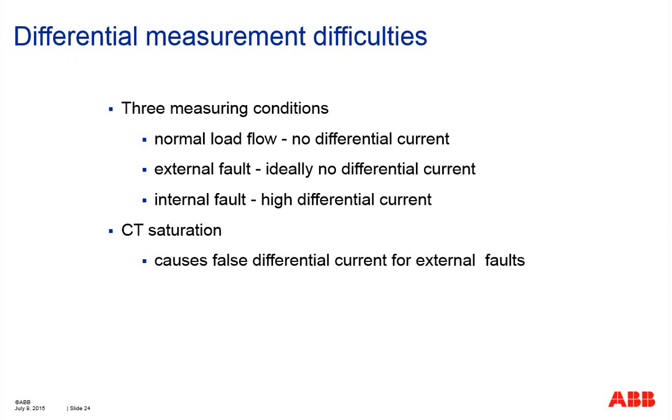However, because of external fault, there is possibility that one of the CTs could saturate, and the saturated CT would provide distorted secondary current that could jeopardize the stability of the relay. Okay? For internal fault, obviously, all the currents are going through the fault inside the protection zone, the relay definitely has to operate. So you will have high differential current.